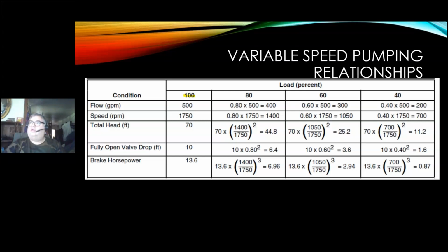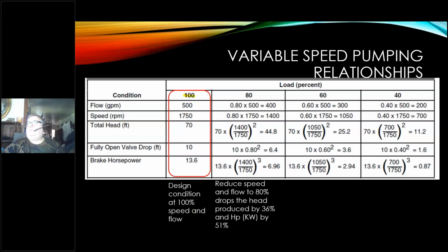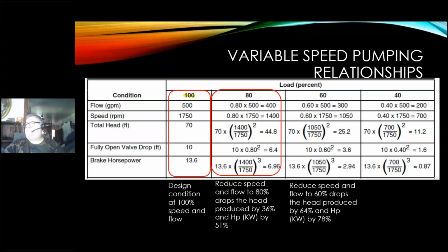We start off at design, okay? Design condition at 100%, 500 GPM at 1750 RPM. The total head is 70, and our brake horsepower required is 13.6. That's actually what we would measure. So we need a 15 horse motor to maintain the 13.6. If I go to 80%, reducing the flow to 80% by reducing the speed to 80%, drops the head produced by 36%, but the horsepower, according to the calculations, drops by 51%, or almost half. Again, that's the cube law. If we go to 60% flow, the head produced drops by 64%. Again, that's the square. But the kW is down 78%.